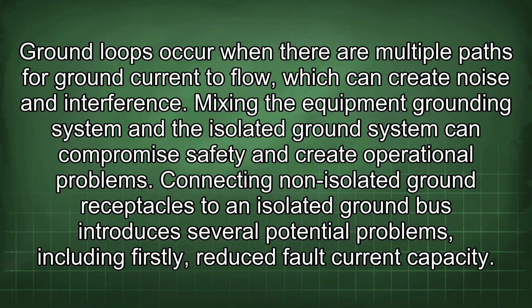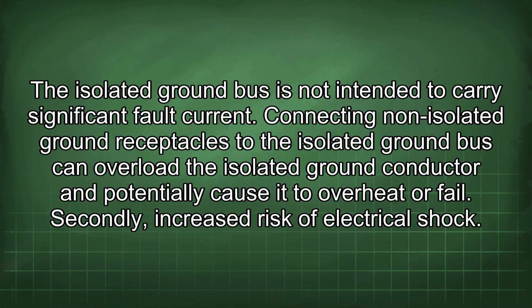Mixing the equipment grounding system and the isolated ground system can compromise safety and create operational problems. Connecting non-isolated ground receptacles to an isolated ground bus introduces several potential problems, including firstly, reduced fault current capacity. The isolated ground bus is not intended to carry significant fault current. Connecting non-isolated ground receptacles to the isolated ground bus can overload the isolated ground conductor and potentially cause it to overheat or fail. Secondly, increased risk of electrical shock.